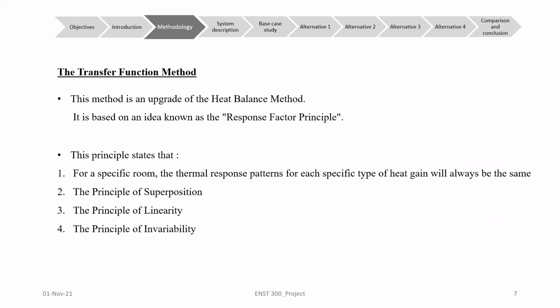An alternative to the heat balance method that is less time consuming and shows high accuracy is the transfer function method. This method is based on the response factor principle. I will explain this principle by an example. The idea is that for a specific room, a 1000 BTU per hour heat gain through the exterior wall will cause the same response over a period of hours as a 2000 BTU per hour heat gain, for example. So the load will change, but the heat gain to load conversion will remain the same.